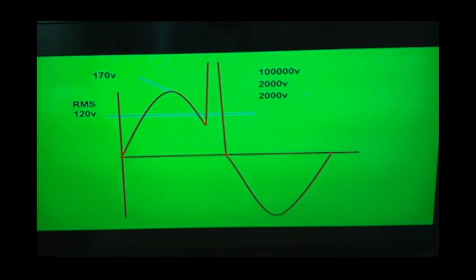Well, under any one of these conditions, if you have a 600 volt meter or a 1,000 volt meter and you measure a transient, the meter has a chance of exploding. The next problem here is that these transients occur in population centers anywhere between 200 to 300 times a day. This is the reason for categories.